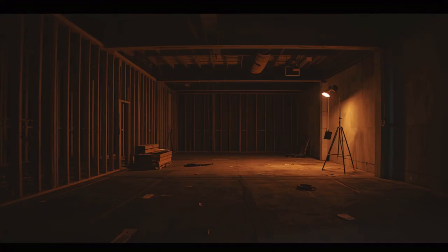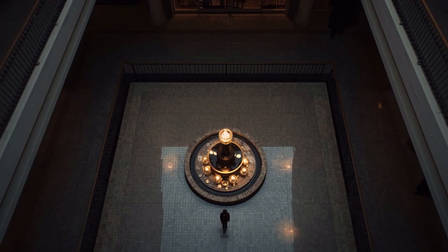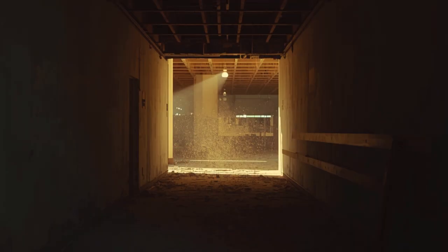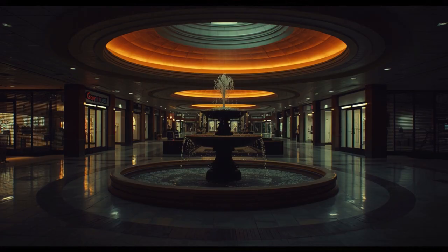And in a space like a mall atrium, where the vertical geometry actively promoted the upward spread of smoke through a connected multi-story volume, the potential for rapid smoke filling of occupied spaces was a genuine and serious concern. The response to this understanding, in the design of 1980s mall buildings, was the development of what were known as smoke control systems. Mechanical systems specifically designed not to suppress fire, but to manage the movement of smoke within the building in ways that protected the occupants' means of escape.